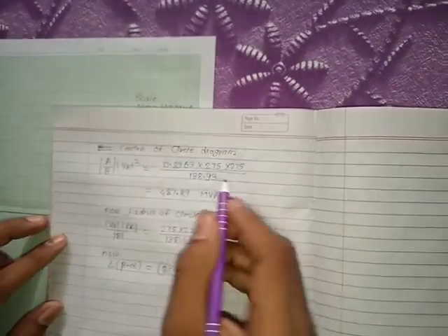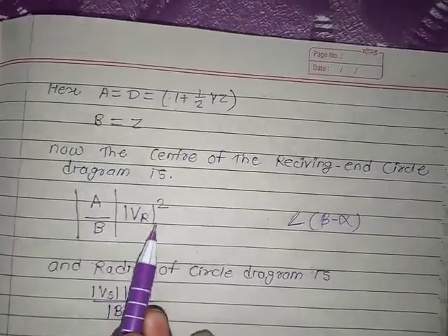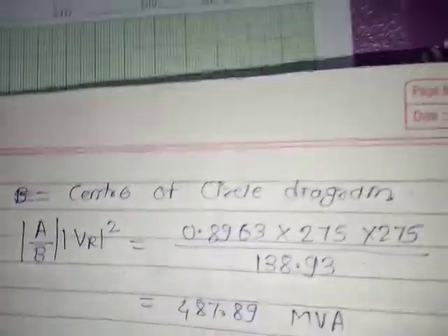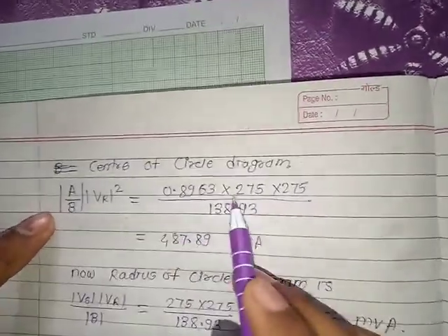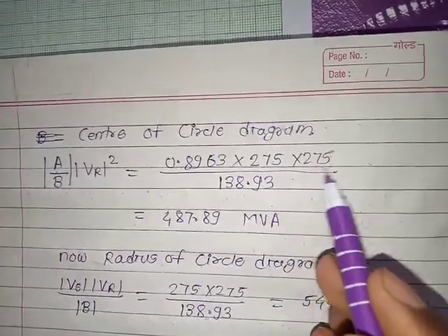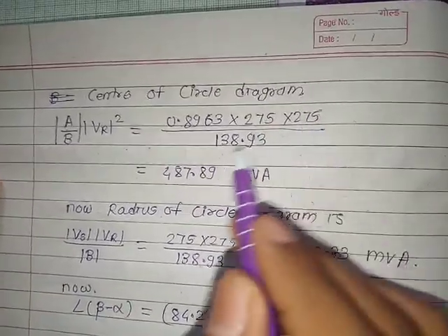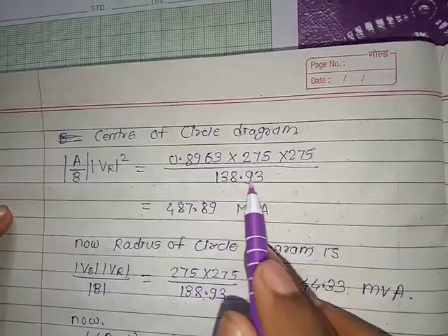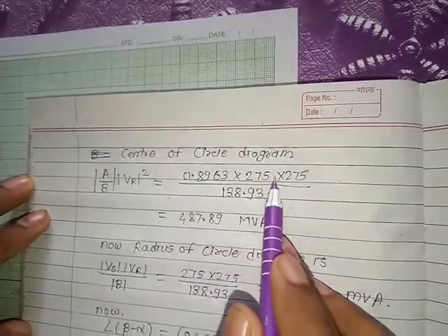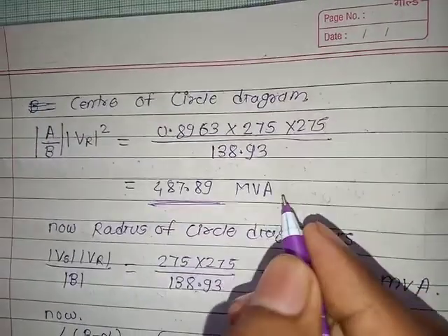Now we calculate the center of the circle using the formula: center = (|A|/|B|) × Vr² at angle β − α. With A = 0.8963, Vr = 275 kV, and |B| = 138.93 ohm, we compute (0.8963/138.93) × 275² = 487.89 MVA. The result is in MVA because Vr is in kV.